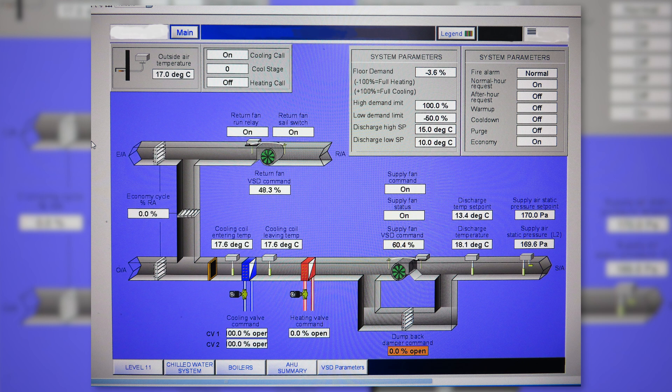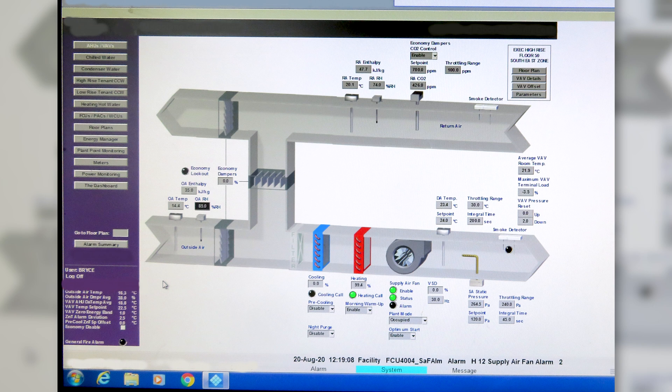In this first example, I'm pretty sure that's an old Johnson Controls BMS system - I remember that blue-purple background. As you can see, we've got a supply and return fan, heating and cooling coils, economy cycle dampers on the left, and on the right our supply temperature and supply pressure controls. There's a box with some parameters for a temperature set point reset strategy, but generally not that different from what you'd expect to find on a modern day graphic.